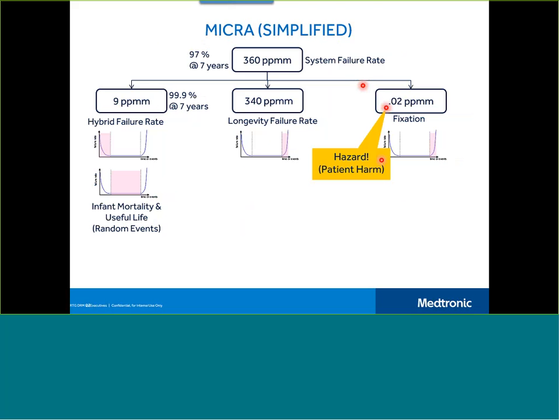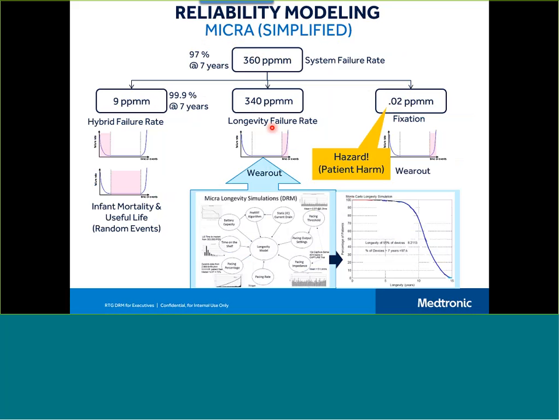So that was just one part of the reliability modeling, and that was actually hazard patient harm, that fixation force. We also cared about the largest part, which is the actual simplified version of the reliability flow down for MICRA. 360 ppmm corresponded to 97% reliability at 7 years. And the biggest part of it was longevity, the battery life, where it would be pacing the heart. So we looked at the longevity and we built a Monte Carlo simulation for that.